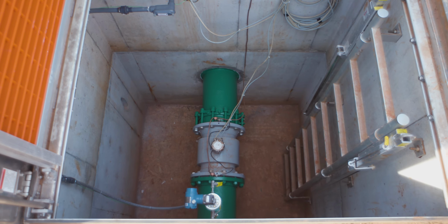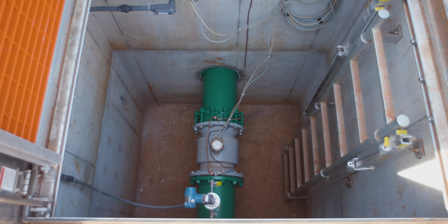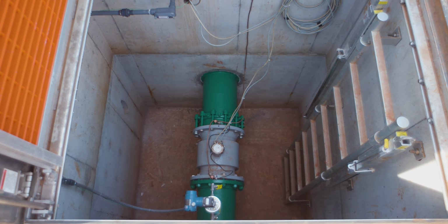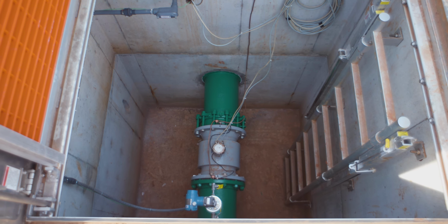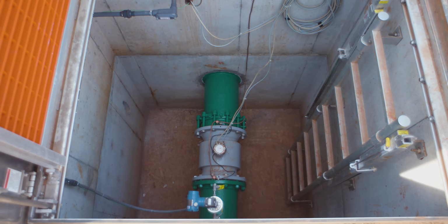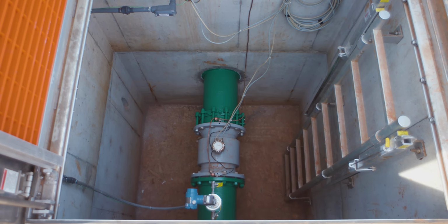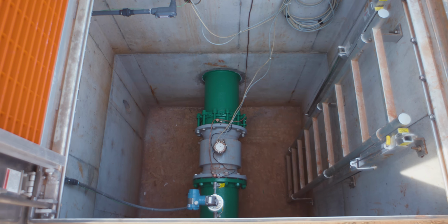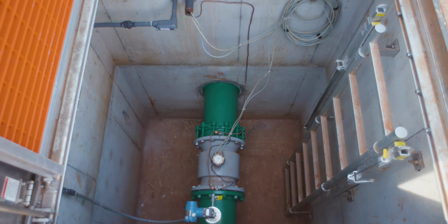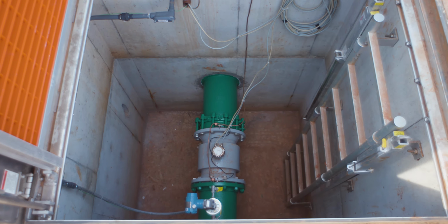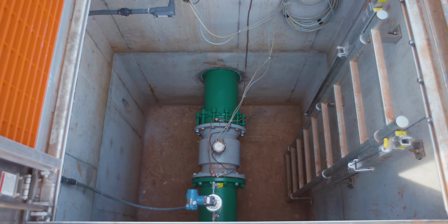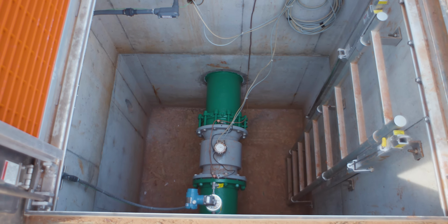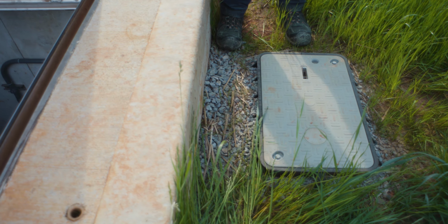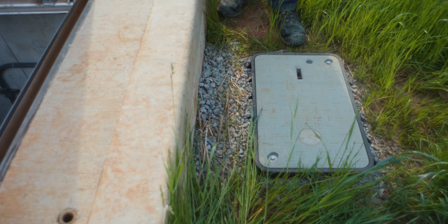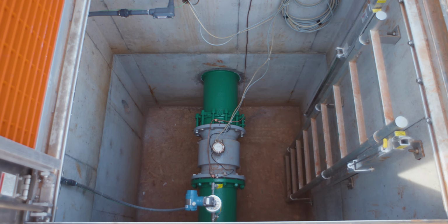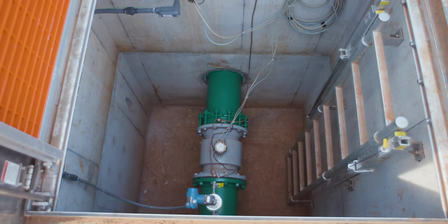The flow meter is highly dependent on a ground. And you'll notice that the ground is not connected in the conduit or anything like that. This is an earth ground. So that earth ground needs to be checked and maintained over the life of this flow meter for it to be accurate and for it to last. And it has grounding rings, but this ground is a backup to the grounding rings in case of corrosion and things like that. The earth ground is in this box right here, and it's a ground rod that's driven down into the earth as a ground reference backup for that flow meter.